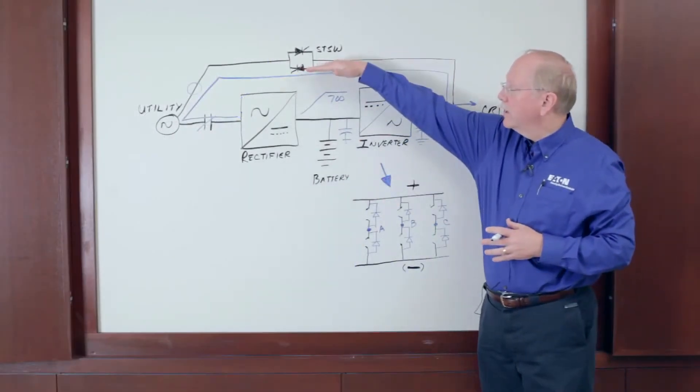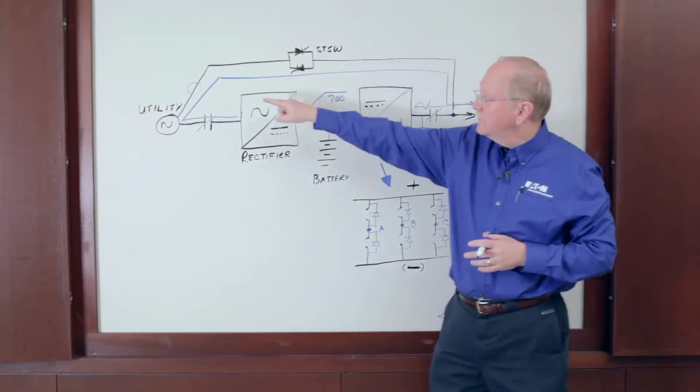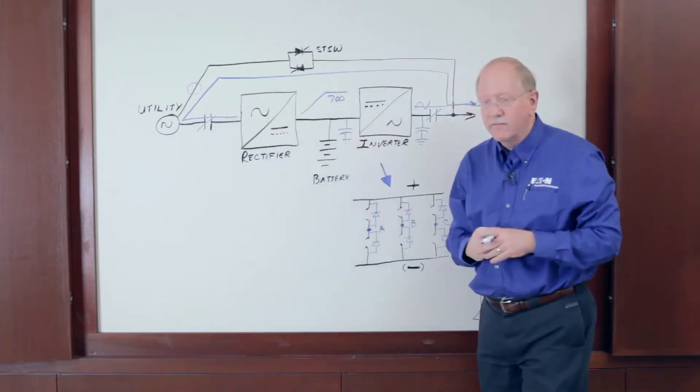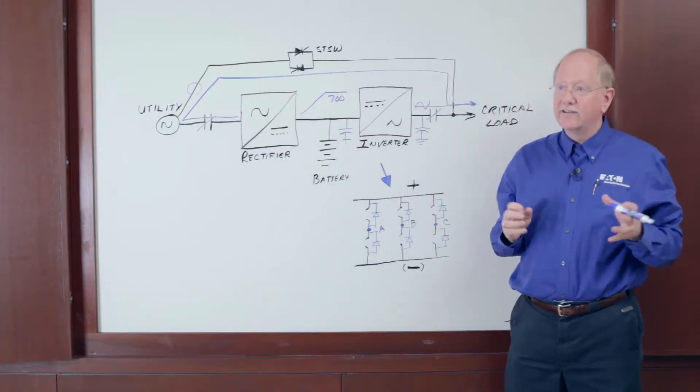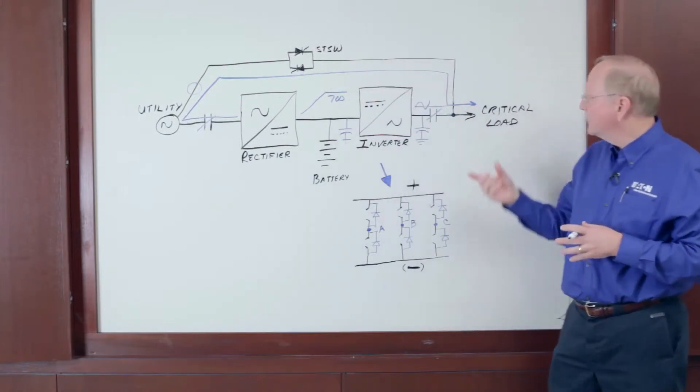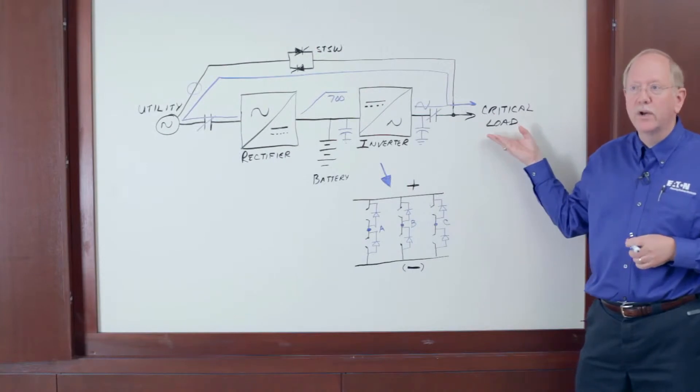So in eco mode, I'll have power through the static switch. If the incoming power becomes disturbed, I can flash on the rectifier and the inverter, and I can do that in as little as two milliseconds, including turning off the static switch. Is that fast enough for the critical devices that we're supporting here?